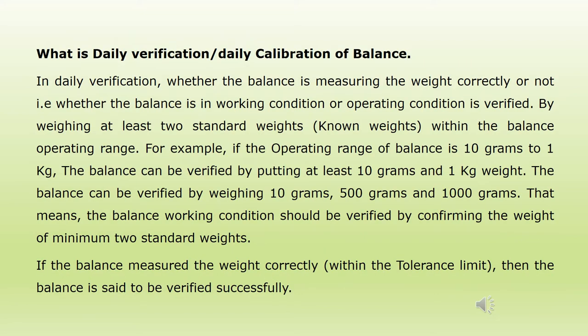What is daily verification of a balance? In daily verification, whether the balance is measuring the weight correctly and is in working condition is verified by weighing at least two standard weights within the balance operating range. For example, if the operating range is 10 grams to 1 kg, the balance can be verified by putting at least 10 grams and 1 kg weights, or by weighing 10 grams, 500 grams, and 1000 grams. If the balance measures the weight correctly, the balance is said to be verified successfully.